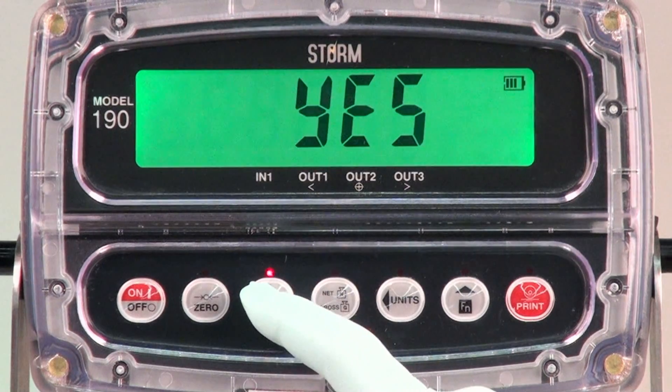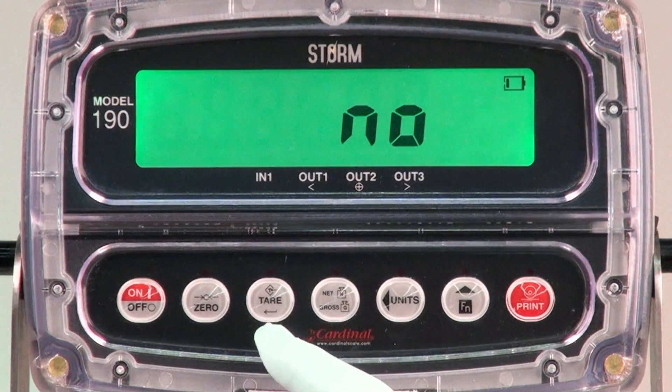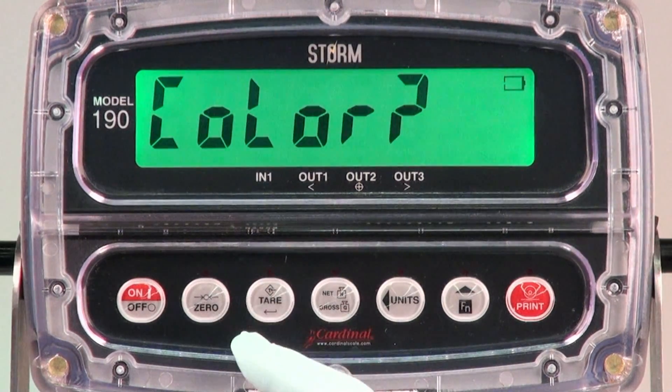At the end of the function settings is a selection for color. This will be for changing the default color of the indicator if checkweigher and the color zone feature are not turned on. In checkweigher mode, the amber, green, and red lights will automatically activate on the preset weight values. So for checkweigher, we'll just say no for the default color.